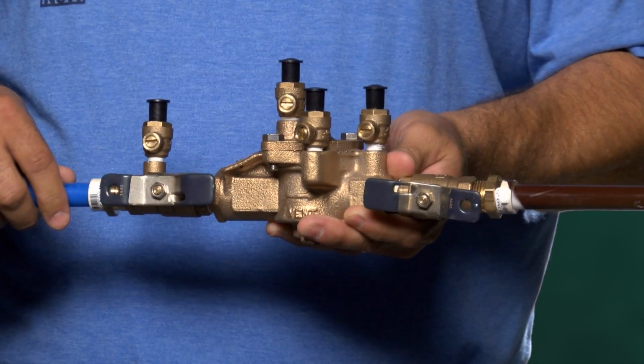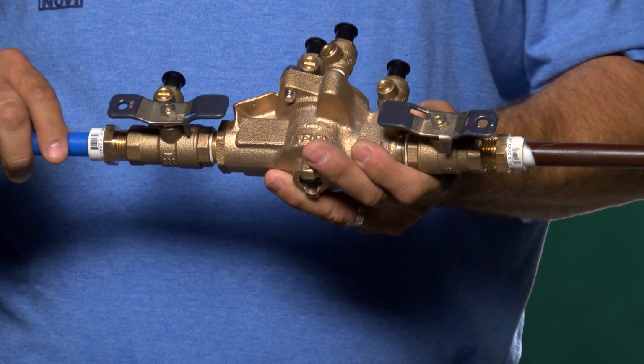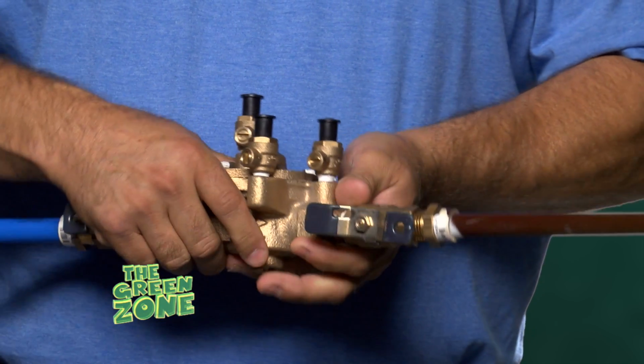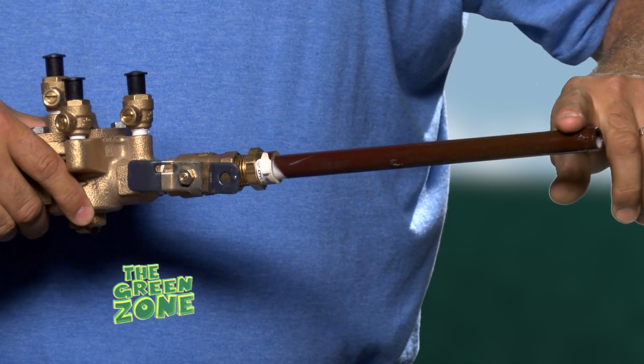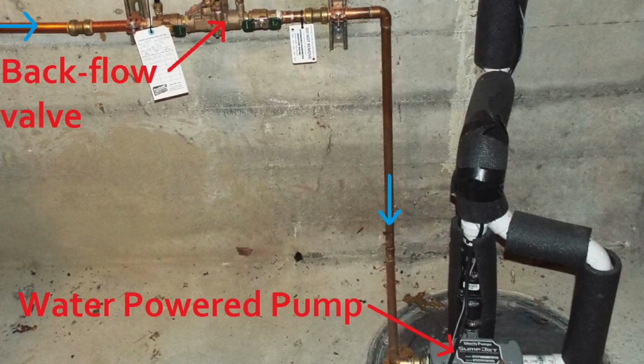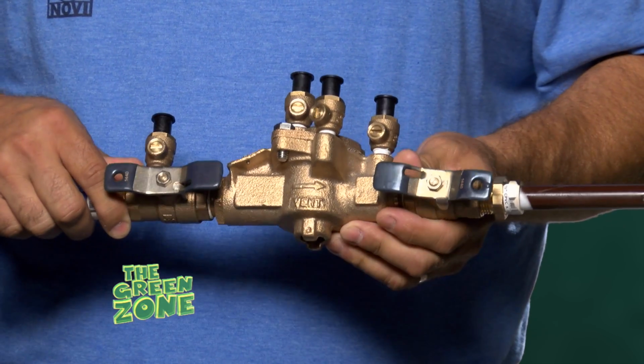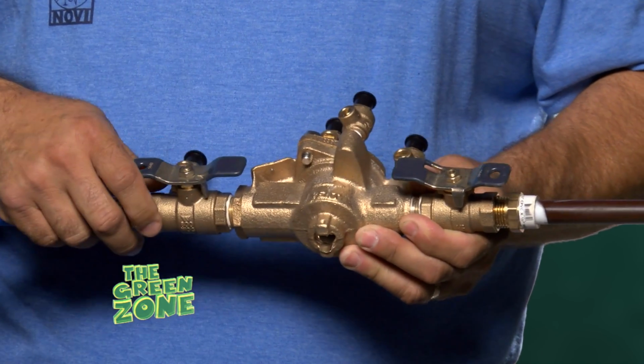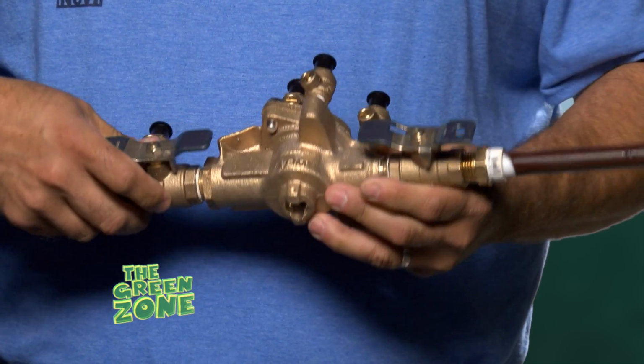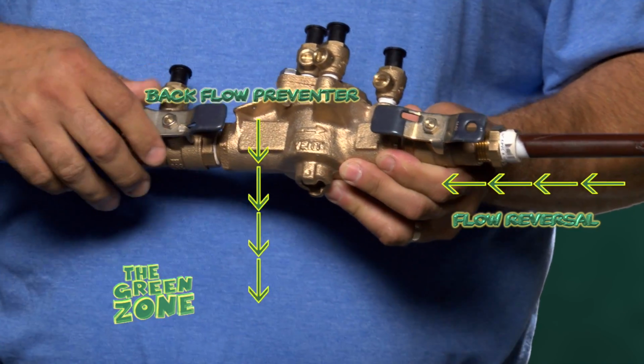These are shut-off valves as part of an assembly. And the testing is done in accordance with the City of Novi's cross-connection control program. But the water flows through here, through the assembly, and this would go to your water-assisted backup sump system. Now, should there be an event that creates a form of a backflow, what this assembly does is it prevents the water from flowing back into here. There's two check valves in here, and what you have is a third component in here, which is a vent. And water would flow out of here pretty steadily if you have a back siphonage or a back pressure event that's happening.